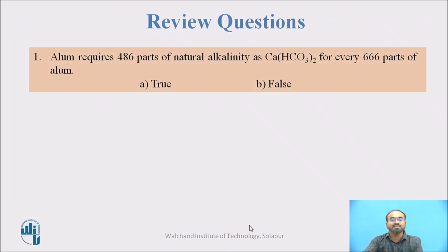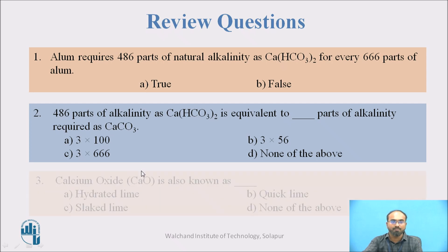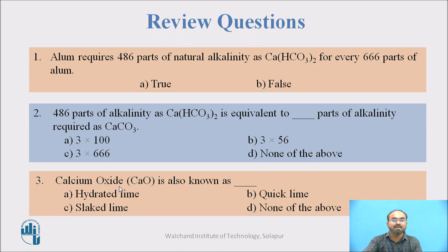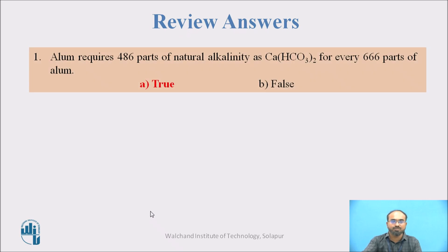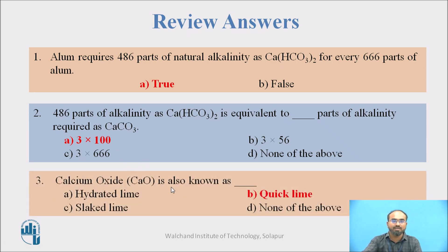Review questions: First — alum requires 486 parts of natural alkalinity as Ca(HCO₃)₂ for every 666 parts of alum; true or false? Second — 486 parts of alkalinity as Ca(HCO₃)₂ is equivalent to how many parts of alkalinity as CaCO₃: 3 × 100, 3 × 56, 3 × 666, or none of the above? Third — calcium oxide is also known as hydrated lime, quick lime, slaked lime, or none of the above? Answers: first is true; second is 3 × 100; third is quick lime.